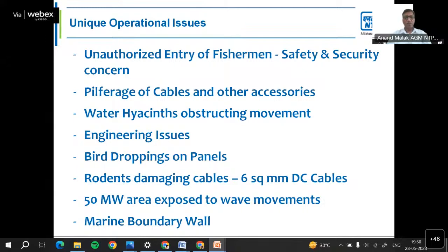After installation and commissioning, we faced problems like unauthorized entry of fishermen, safety and security concerns, pilferage of cables and other accessories, and water hyacinth obstructing boat movement. Some engineering issues were there too, including bird droppings on panels requiring regular cleaning, and rodents damaging the 6 square mm DC cables, leading to inverter tripping on ground fault. The 50 megawatt area is also exposed to large wave movements. One more proposal is about the boundary wall, which is another challenge we are looking into.